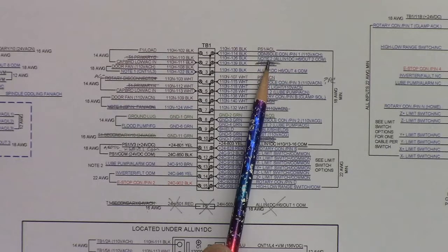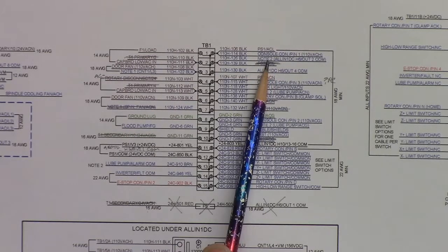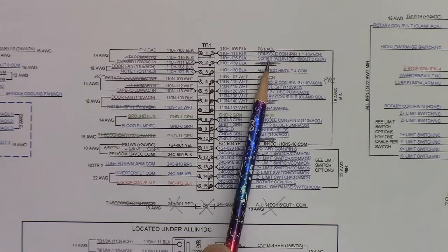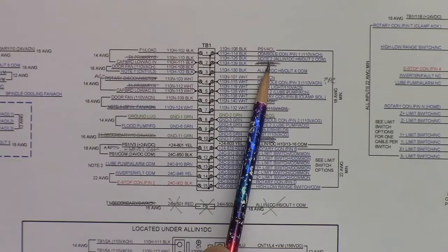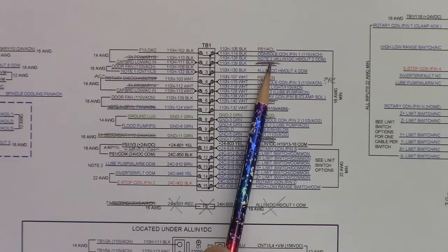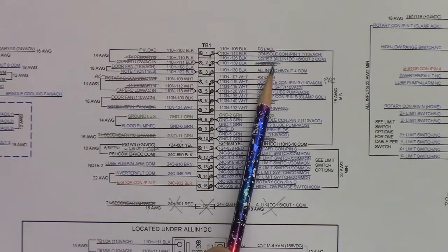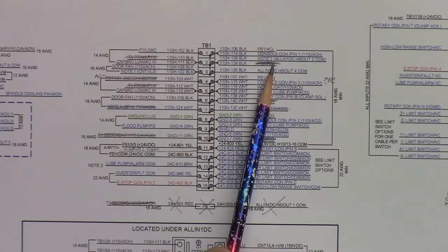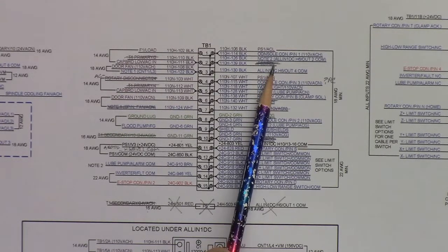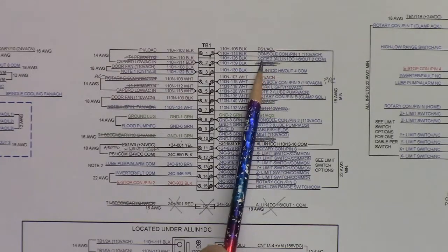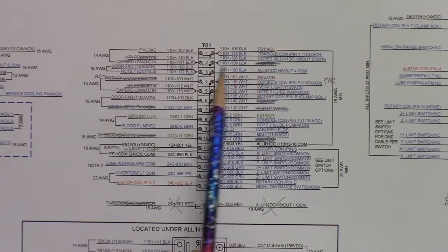On the B side here, looks like it also provides power to the console. I'm not using a console. I'm just going to use a touchscreen monitor on my machine. There's a note here for note two. If I go take a look at note two, it talks about the lube pump. If you're using a 110 volt lube pump, follow this section. Using a 220 volt lube pump, it tells you how to wire it there. So that's feeding the lube pump.